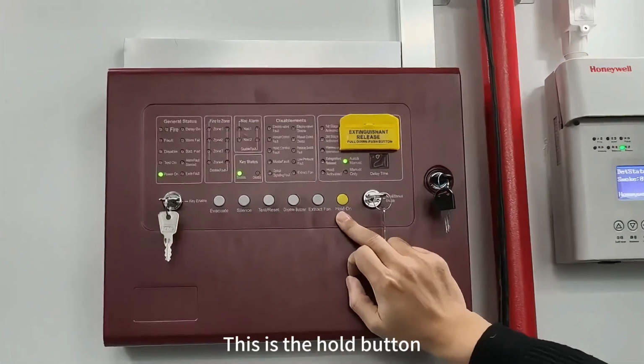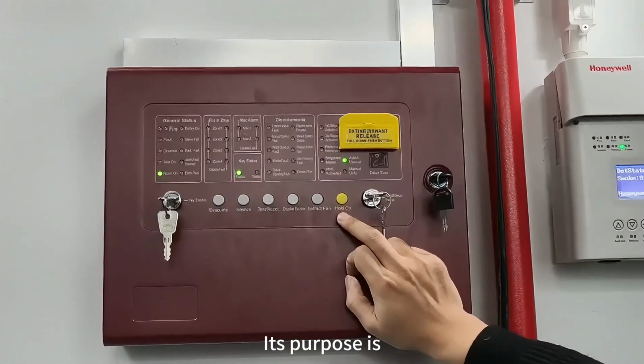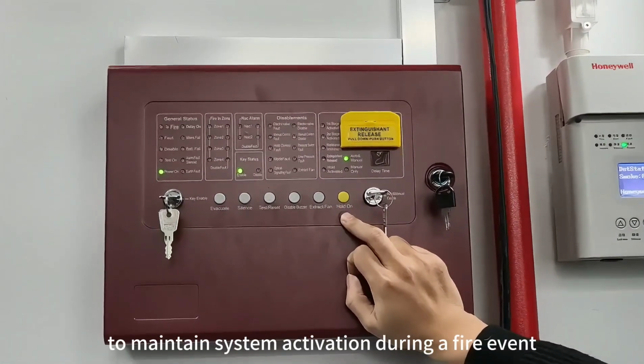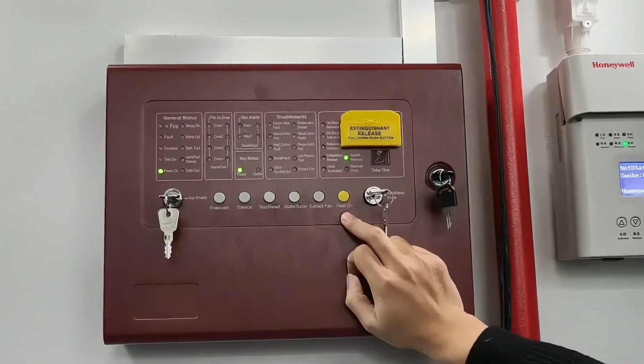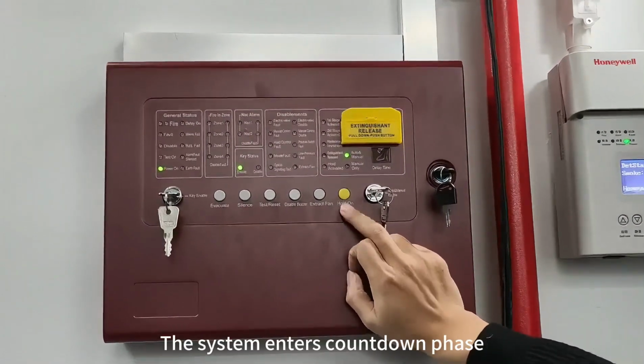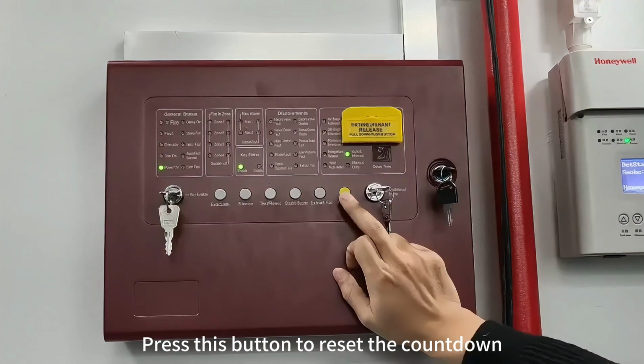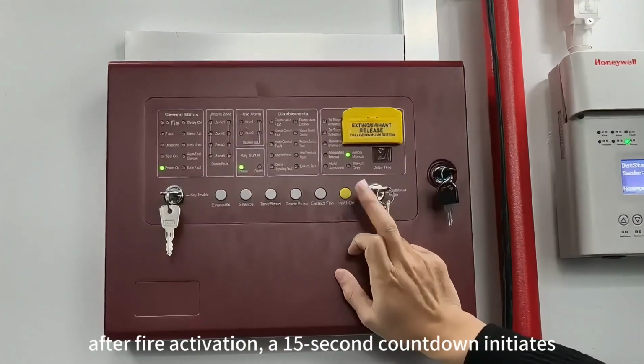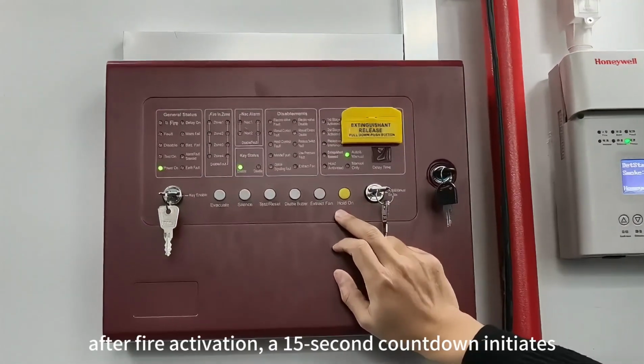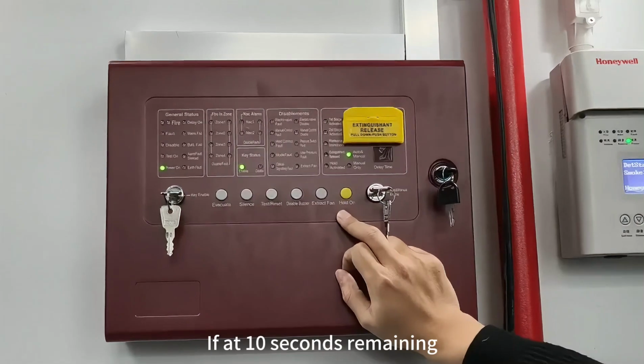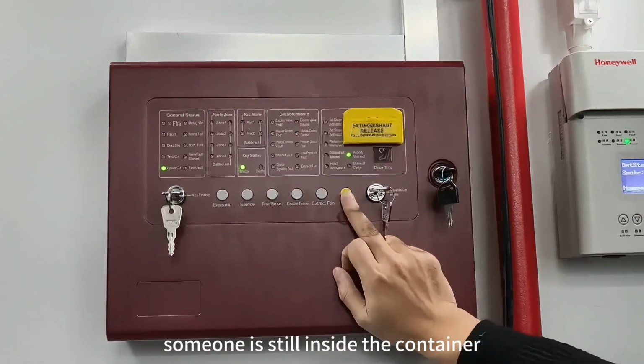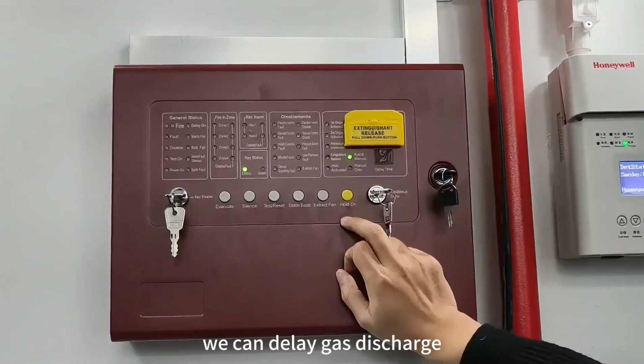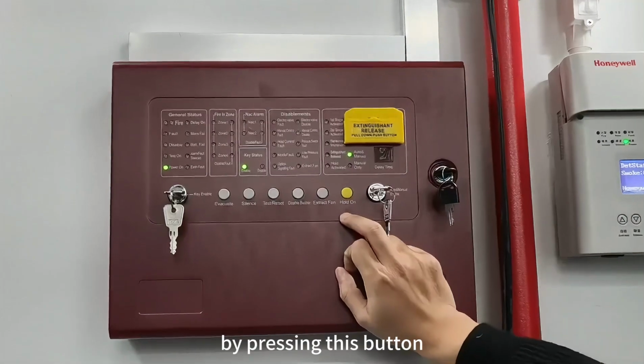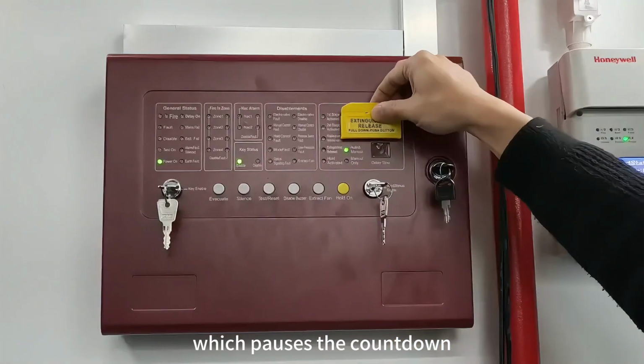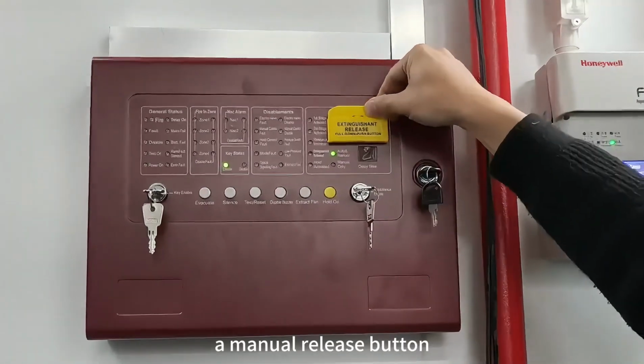This is the hold button. Its purpose is to maintain system activation during a fire event. When the system enters the countdown phase, press this button to reset the countdown. For instance, after fire activation, a 15-second countdown initiates. If at 10 seconds remaining, someone is still inside the container, we can delay gas discharge by pressing this button, which pauses the countdown. Here we also have a manual release button.